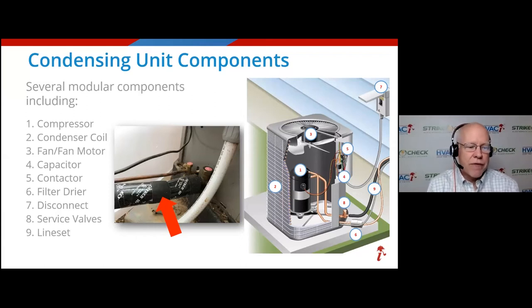So now you have a little bit more information on those, and your key takeaway for adjusting, always think repair on a line set before you replace a line set. Even if we decide we have to replace the outside and inside equipment, you probably can save the line set. We can flush it out with an industry approved flush kit, and then put the inside and the outside units in, and you could save hundreds and hundreds of dollars that way. So if it's repairable, repair it.